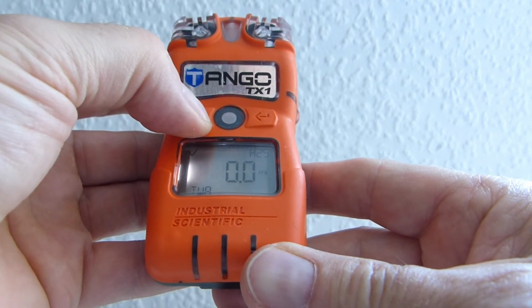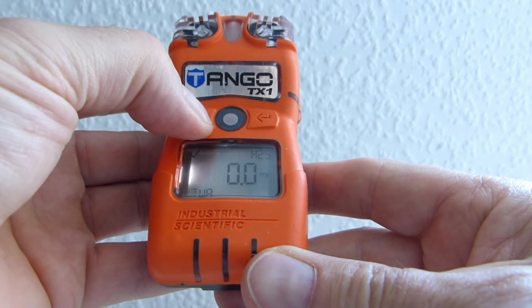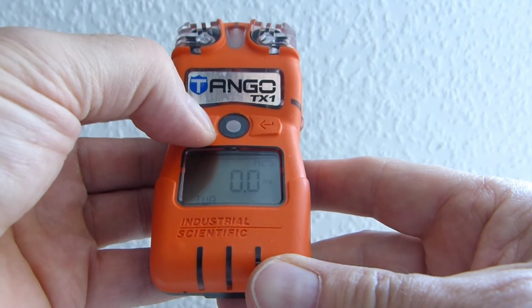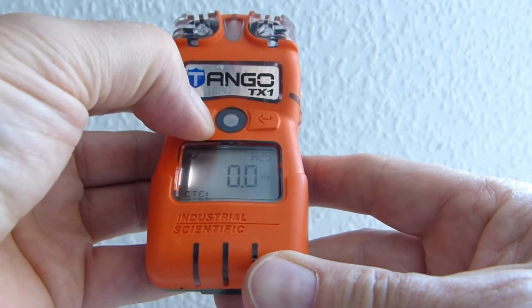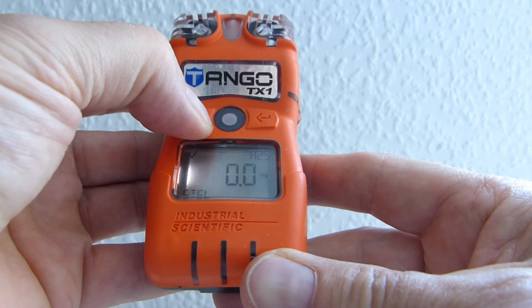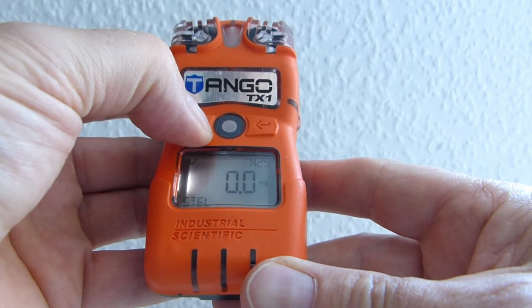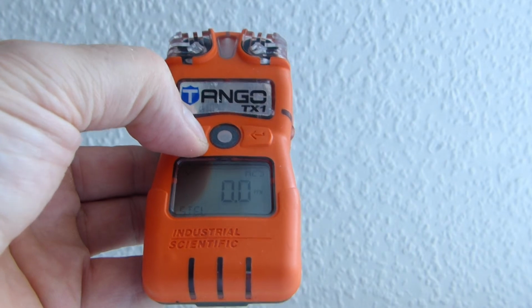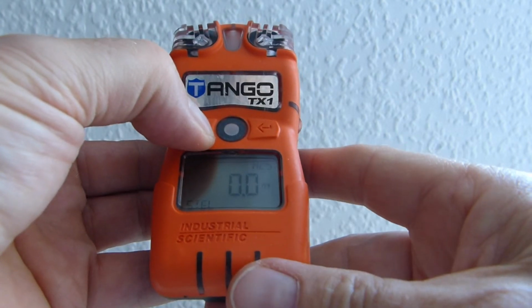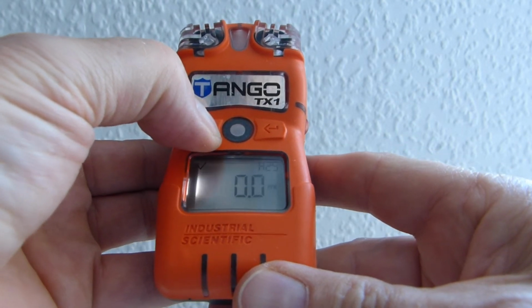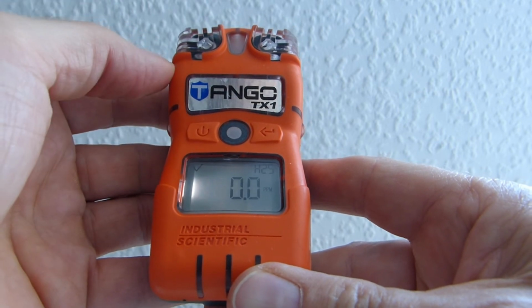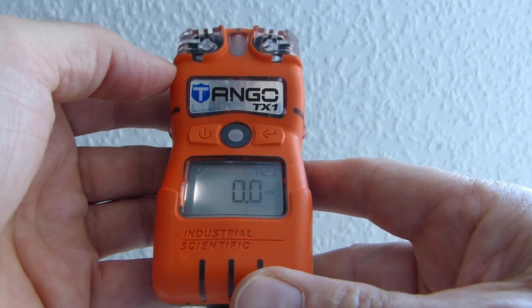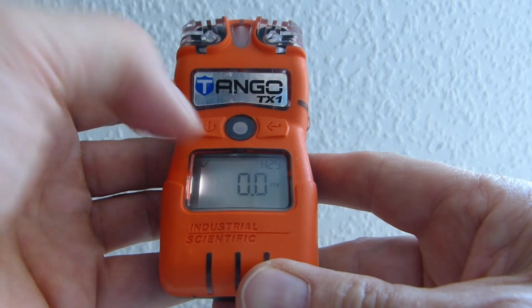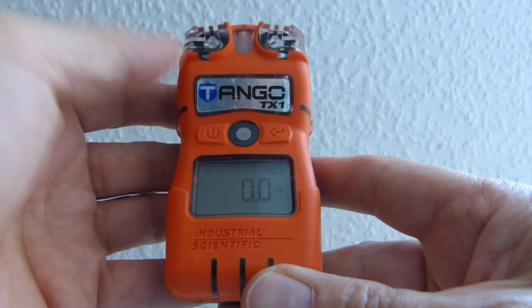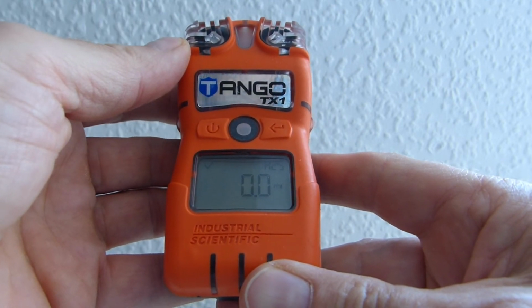This is the TWA alarm, which is an alarm weighted over 8 hours of your working day. The STEL alarm is a short-term alarm for 15 minutes over the last time that you have been measuring. And you go back to the main screen, which happens automatically after a while, or you just toggle by pressing the left button back to the main screen.